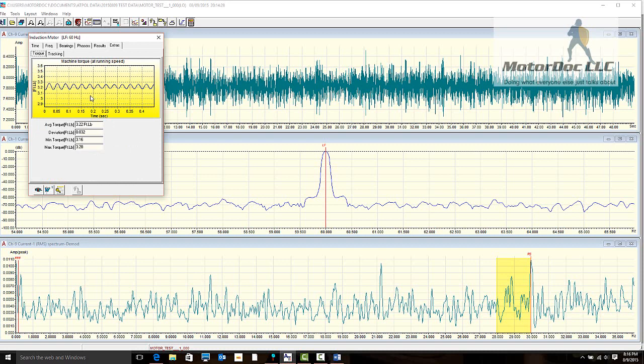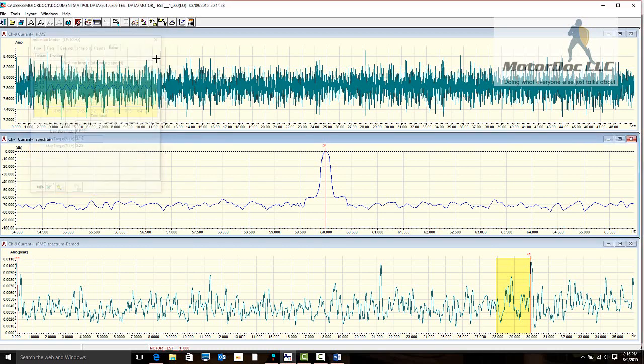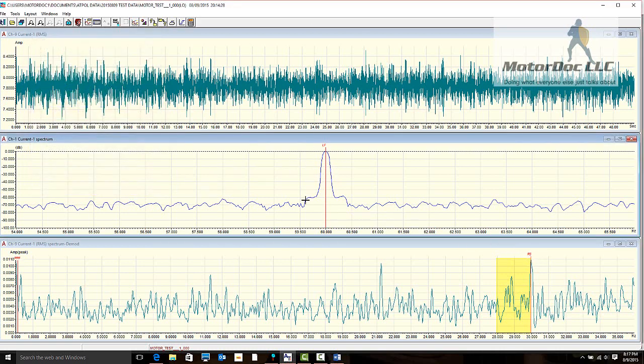We can also take a look at my torque ripple. This is a new piece that comes with version 6.31 and it is extremely powerful. So it's selected a running speed and the line frequency. There's some little peaks here which are kind of interesting. Let's take a look also at the high frequency data.